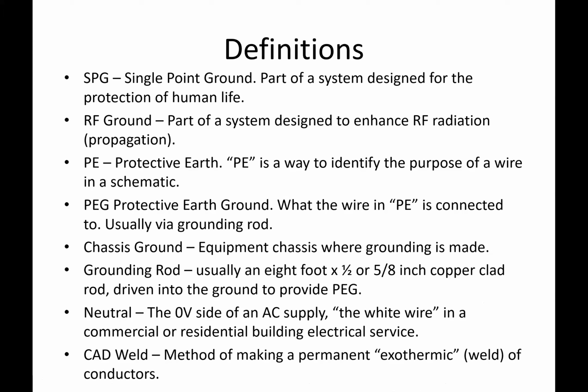PEG, protective earth ground, is what the wire in PE is connected to, usually by a grounding rod. Chassis ground is where the equipment chassis grounding is made, usually a screw or bolt on the back of a device where you would connect the grounding wire. A grounding rod is usually an 8 foot by 1/2 or 5/8 inch copper-clad rod, driven into the ground to provide PEG.